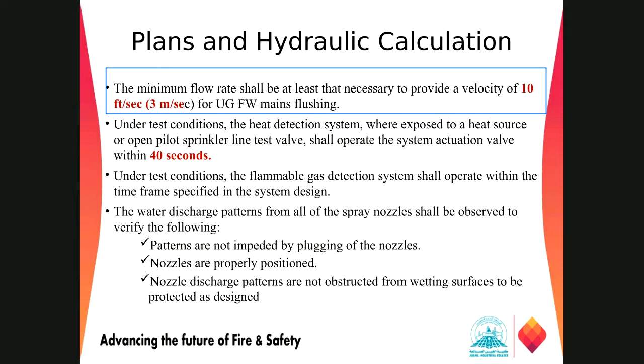The next one they have is the 40-second requirement, right? When the heat detector or a fire detector detects a fire when exposed to a heat source, the system should activate within 40 seconds, right? So 40 seconds is the time between the detection of a fire and activation of our water spray system. Under test condition, the flammable gas detection system shall operate within the time frame specified in the system design. So it is based on the system design how we are going to do the setting in those detectors.